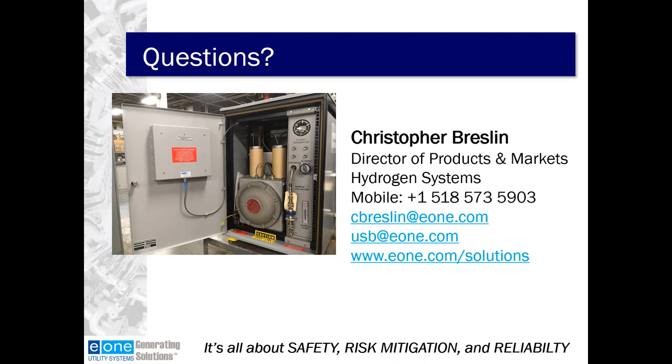Does the verification filter need any maintenance? Does it have to be replaced at a certain point in its life cycle? Yes. When you press the verification filter button, you want to make sure that flow and output stay the same. If you see a decrease in flow when you press the verification filter button, it typically means the filter is clogged and it's time to replace it. That's one of the reasons we have you do that test — it will help you decide when that needs to be done.